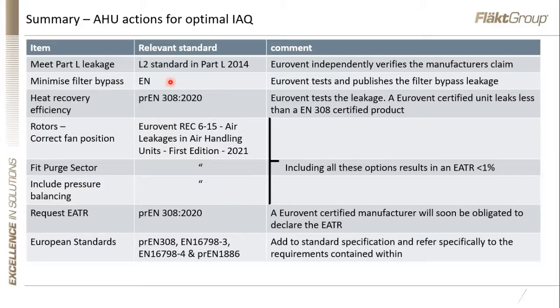I've just realized I've made a little bit of an error because I haven't filled in the standard, but it's EN 16798-3 and 1886. Eurovent tests and publishes the filter bypass leakage. The heat recovery efficiency needs to be in accordance with EN 308. Again, Eurovent tests this, and a Eurovent certified unit leaks less than an EN 308 certified product. When it comes to rotors, put the fans in the correct position, fit the unit with a purge sector, and include pressure balancing. The manufacturer is in theory capable of doing all of those things. There is a lot more detail in the Eurovent document, and if you include all these options, the result is an EATR of less than 1%.